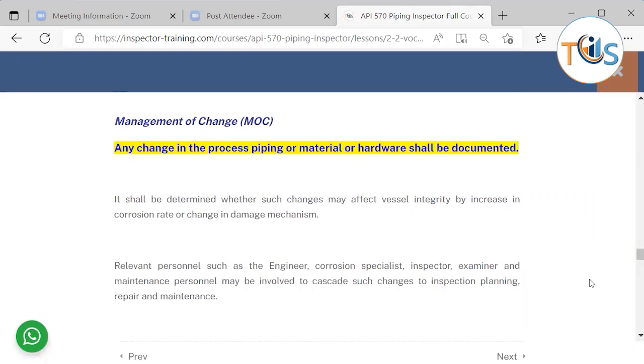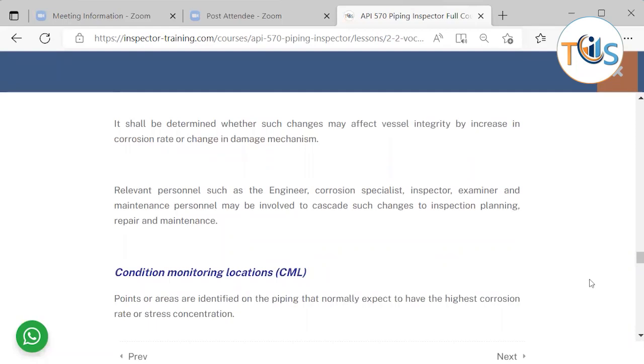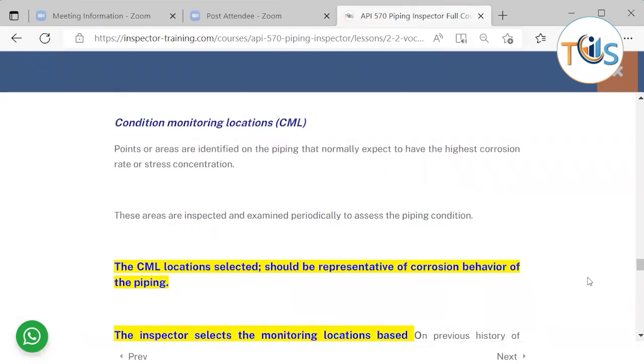Management of change applies when piping was designed for a particular range but you have changed the material, any fabrication parameter originally intended, or the operating parameters. This change must first be documented — that is very important. You also need to assess whether the change affects piping integrity, for example by altering the corrosion rate or changing the damage mechanism due to a change in fluid. Relevant personnel such as the engineer, corrosion specialist, inspector, examiner, and maintenance personnel also need to be involved to see how the change affects their scope of work.